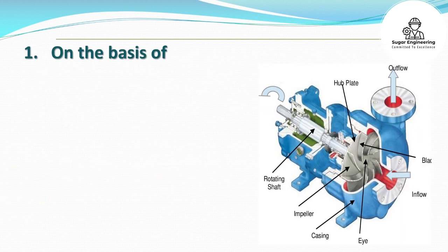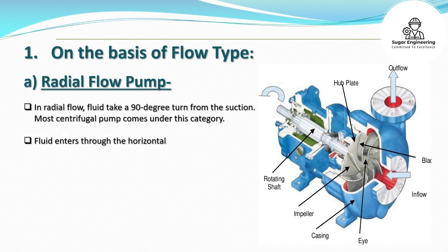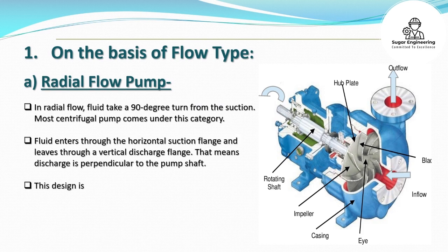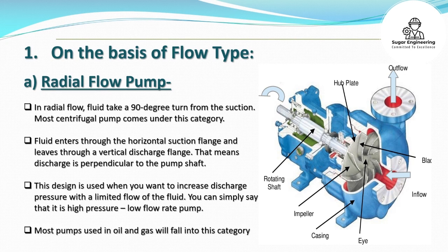On the basis of flow type: A. Radial flow pump. In radial flow, fluid takes a 90-degree turn from the suction. Most centrifugal pumps come under this category. Fluid enters through the horizontal suction flange and leaves through a vertical discharge flange, meaning discharge is perpendicular to the pump shaft. This design is used when you want to increase discharge pressure with a limited flow — it is a high pressure, low flow rate pump. Most pumps used in oil and gas fall into this category.